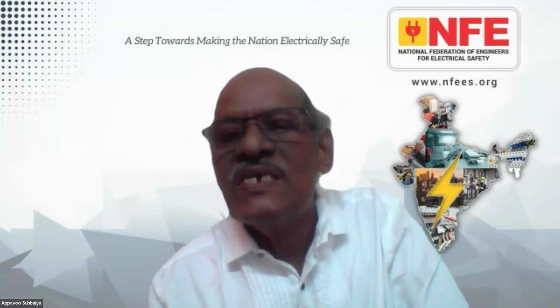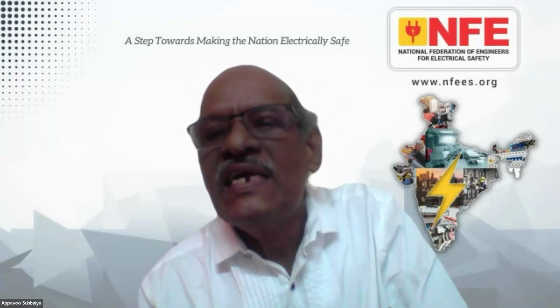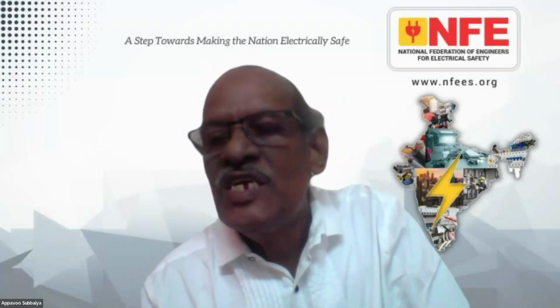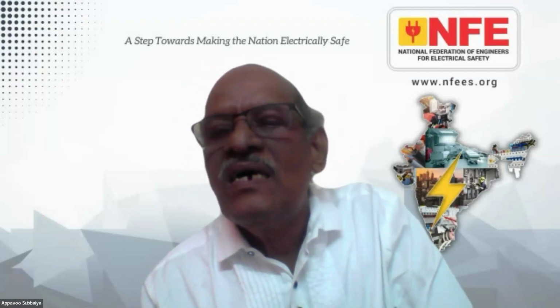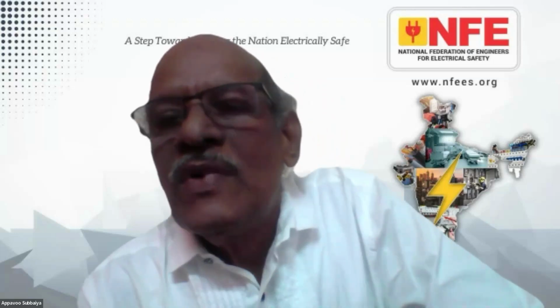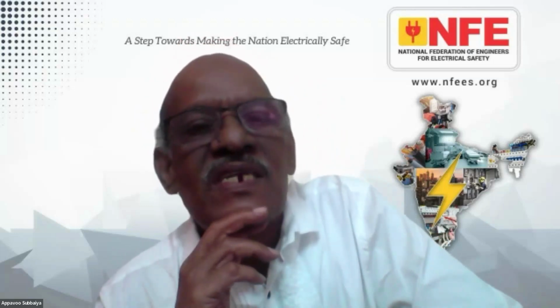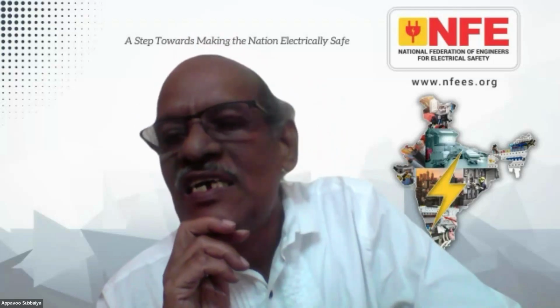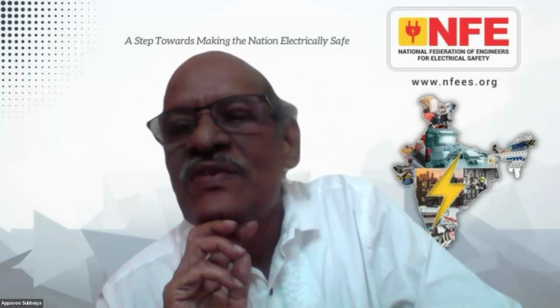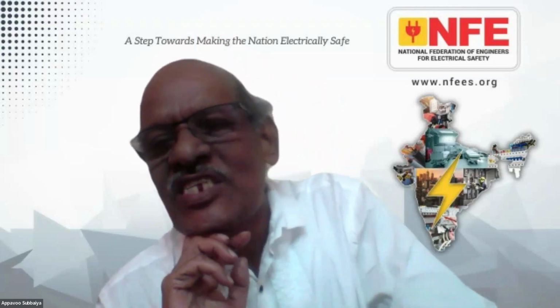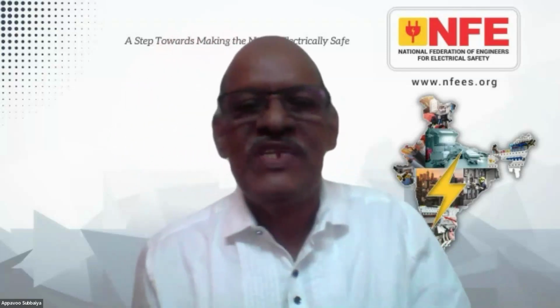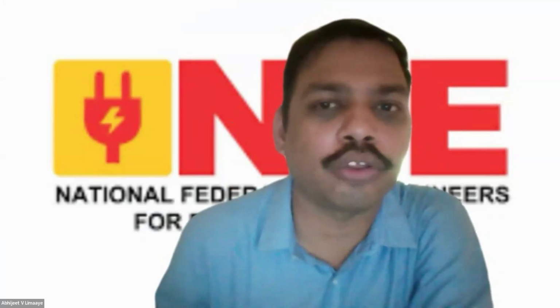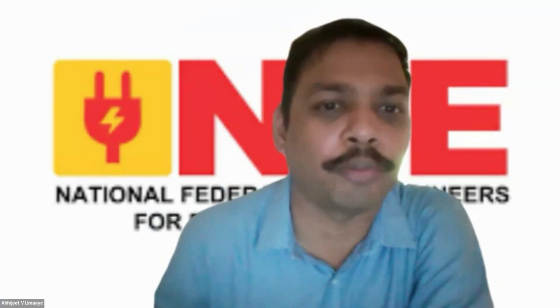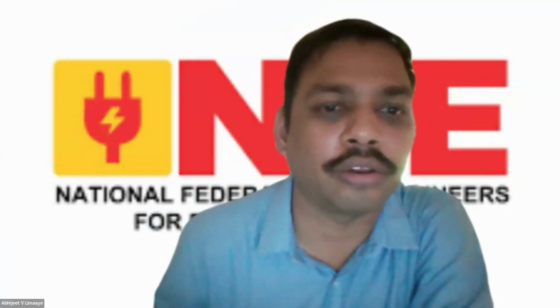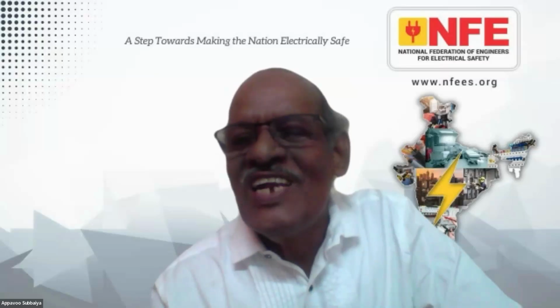Next question is from Mr. Kiran Patni. Any regulation for maintenance of bus duct in high-rise buildings? Mr. Abhijit, can you say anything, any recommendation on this? There is no regulation, but there are established standard practices for maintenance. There is a standard for how the bus duct should be installed, and a standard for how the selection should be made, but I don't think there is any regulation which talks about maintenance. Regulation simply says observe the standards.